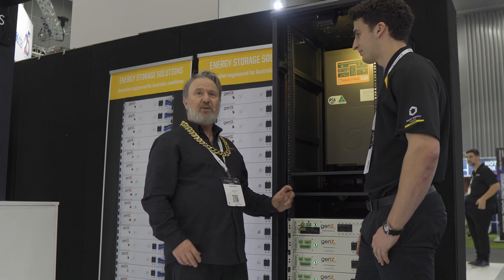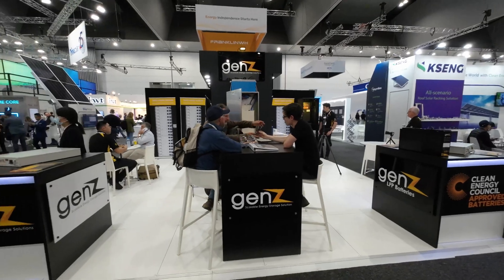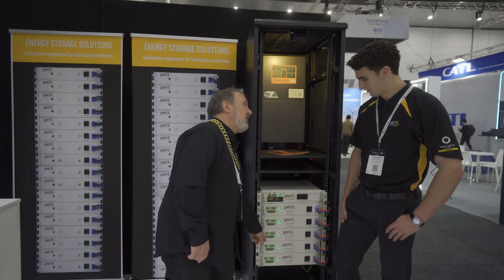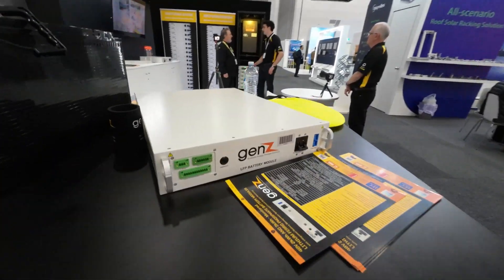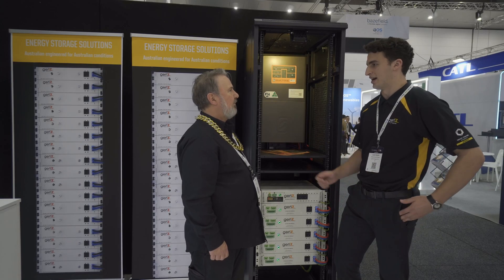So for a self-managed battery, it's got all the functionality that you expect from a managed battery system. Exactly. So it can communicate all of that from every battery module, through all these data connections. This six-pin connector that you see at the front panel here has an RS485 line and a CAN bus line that transmits information up and down the rack.